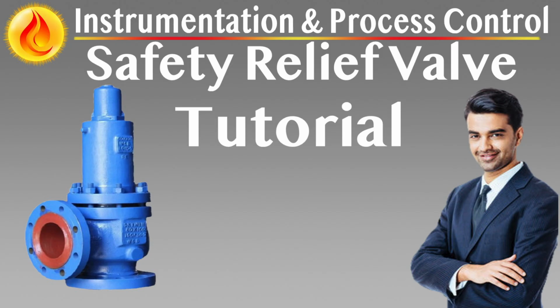Key material considerations: resistance to sulfide stress cracking, selection of low hardness, qualified heat-treated steels, post-weld heat treatment, PWHT, as necessary for weld integrity. Relief valves must be documented and traceable to prove full compliance with these standards.